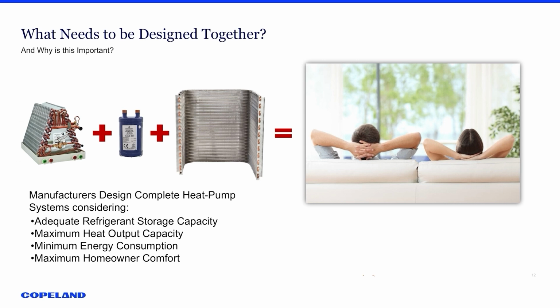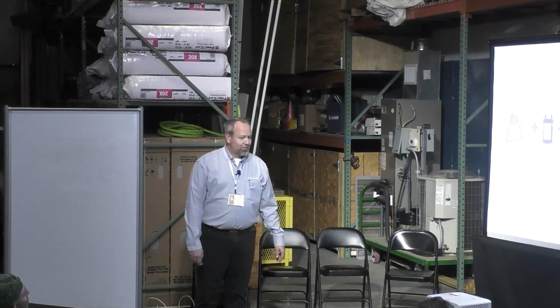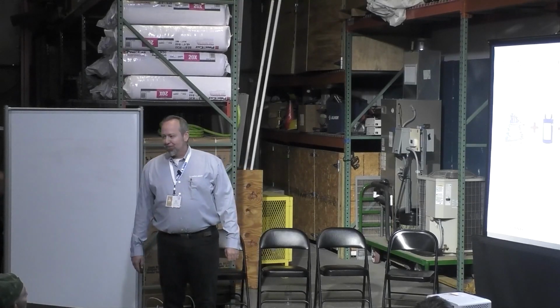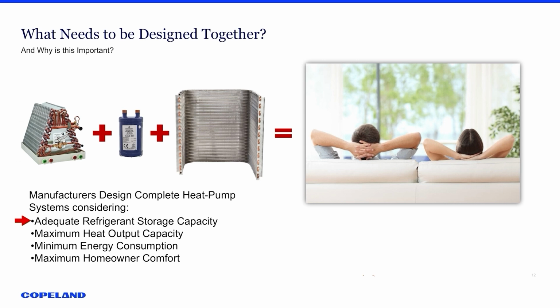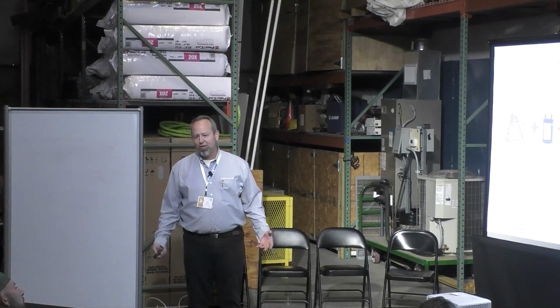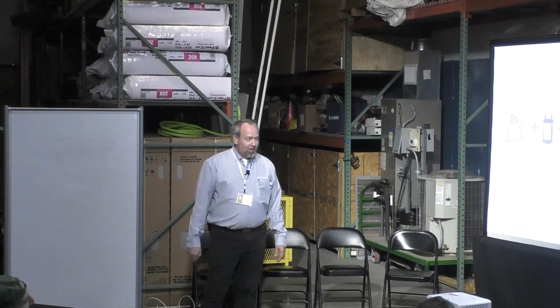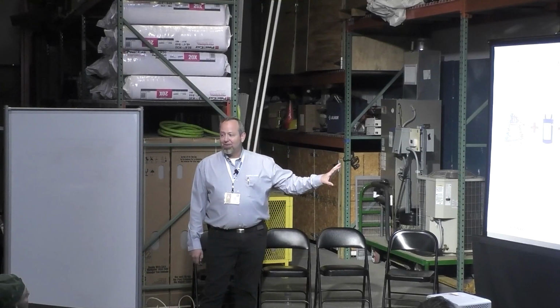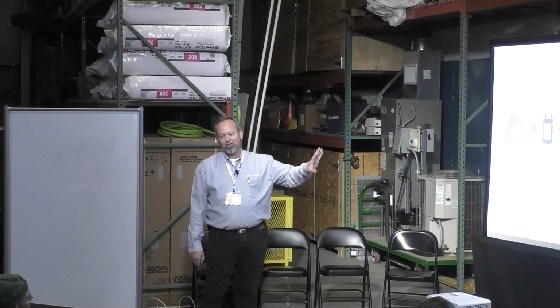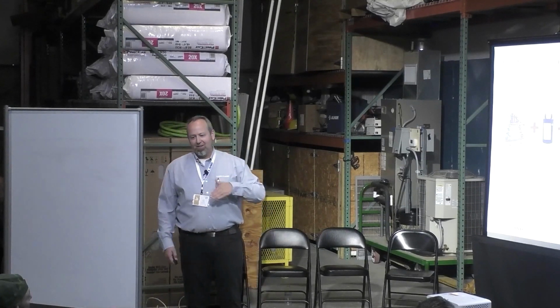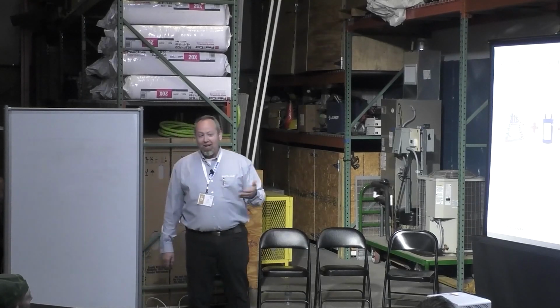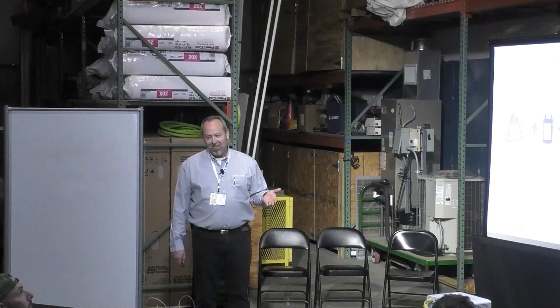And here's what you're going after. Adequate refrigerant storage capacity. You don't have issues with pulling Freon and replacing it. Sorry, I say Freon. It's refrigerant, I know. That's another story. We'll skip that one for now. Maximum heat output capacity, minimum energy consumption, and homeowner comfort. All those things are compromised when you don't match that system up together. That's the first step in getting a dual fuel system installed properly, is having the heat pump system match properly. If you have issues here and you're going with dual fuel, you're going to have a layer on top of a layer trying to figure out what the issue is, where the problem is, and that could make it more difficult to diagnose.